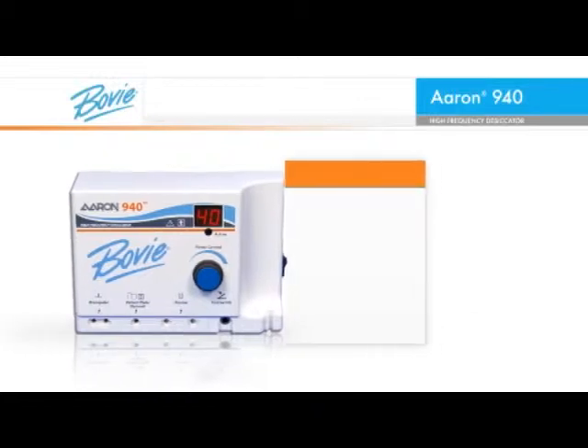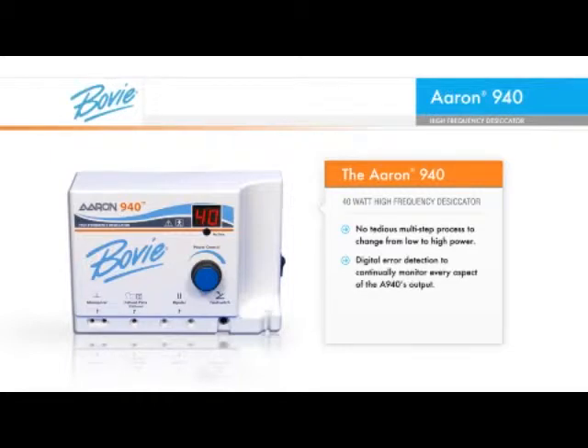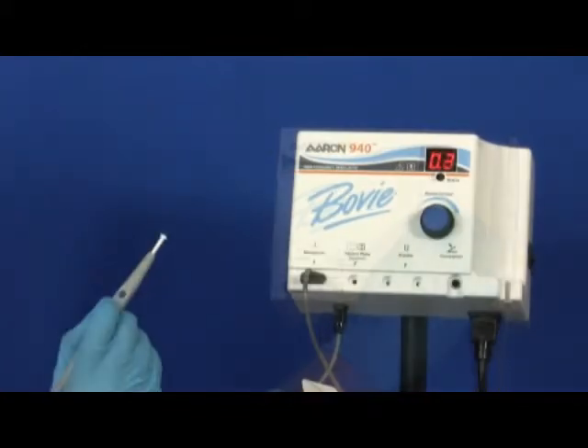The Aaron 940, Bovie's 40-watt high-frequency desiccator, forever removes the need to go through a tedious multi-step process to change from low to high power. This generator has digital error detection and continually monitors every aspect of the A940's output. It allows doctors to change power settings with one action, using the rotary power control dial or the up-down buttons on the autoclavable handpiece.